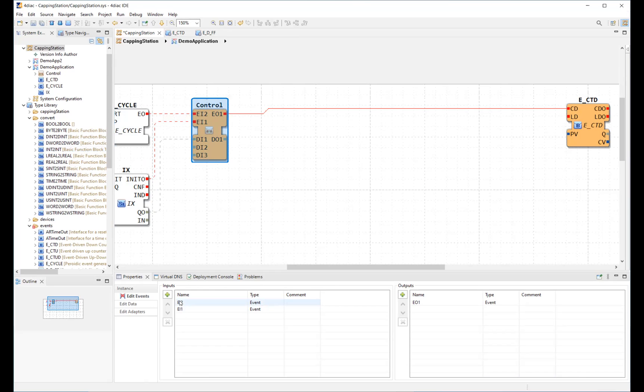Function block types or sub-application types can be instantiated in the application. Please note that all names in a 61499 model must be valid identifiers. The rules are equivalent to programming languages where names need to start with a letter and only contain alphanumeric characters. No special characters are allowed and names cannot start with a number.